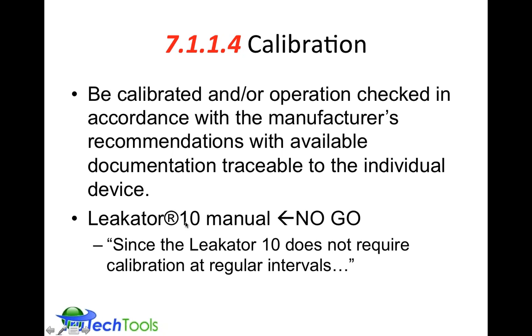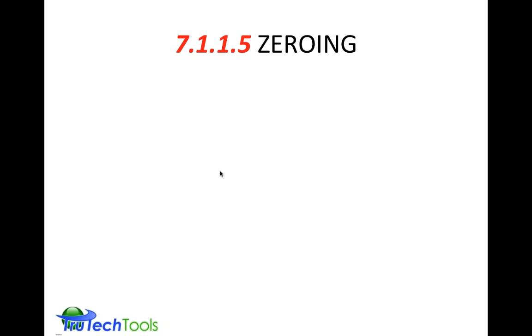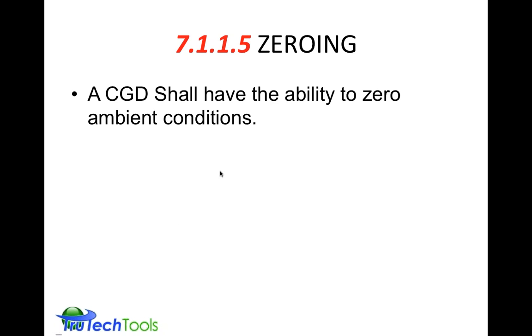We'll be talking about different products, and these are just facts. These are not in any way meant to slight any particular brand of product or name a product, but the Leakator 10 by Bacharach is a no-go because it does not require calibration at regular intervals, which means it cannot be calibrated. So my interpretation with regard to the BPI standard is a Leakator 10 is a no-go because it cannot be calibrated. We'll also see another reason that it cannot be used in a moment too.